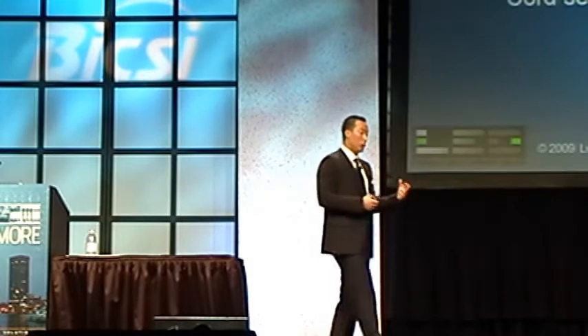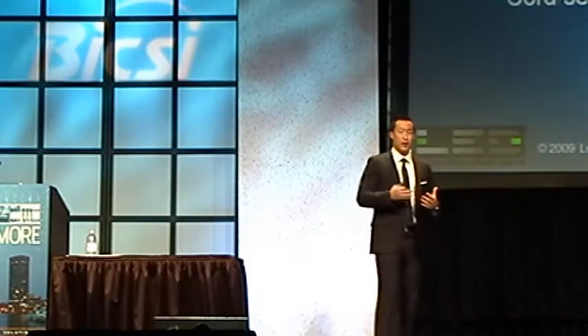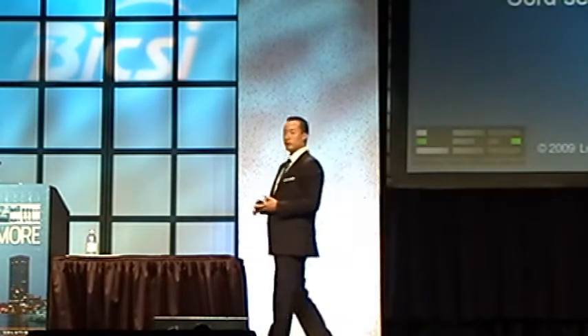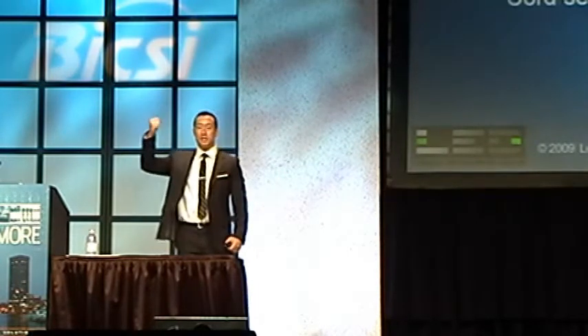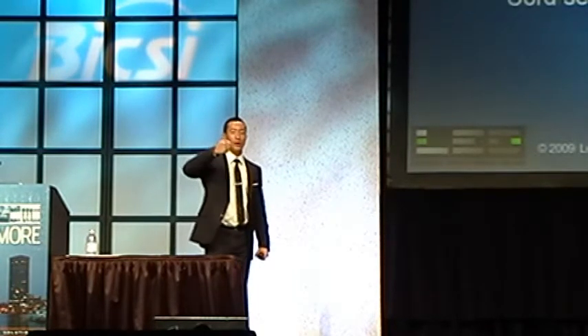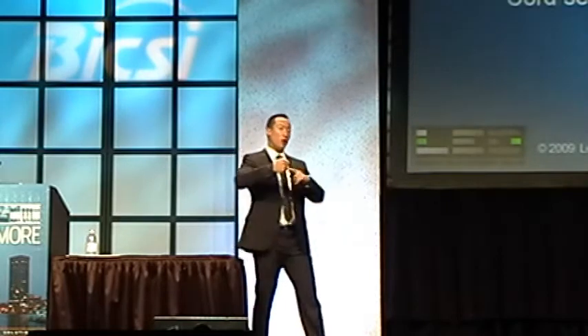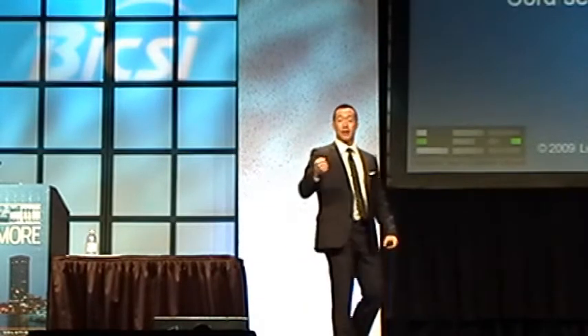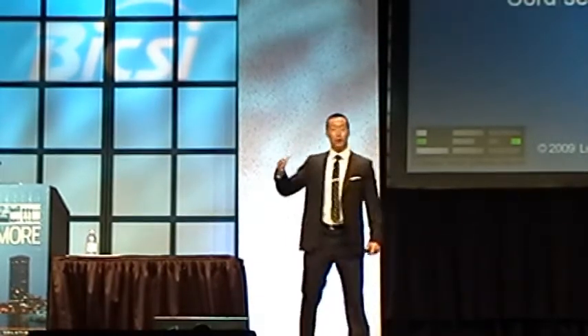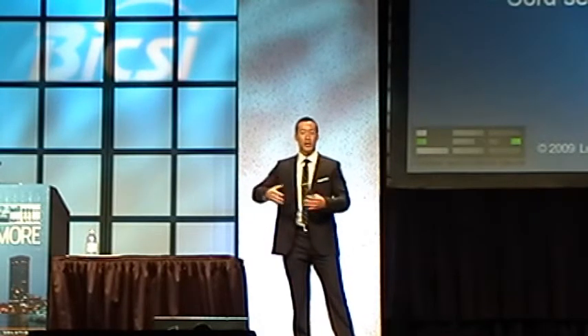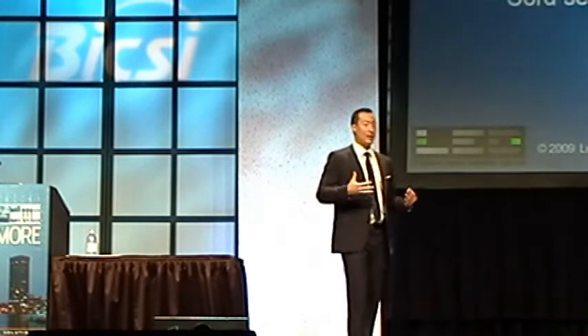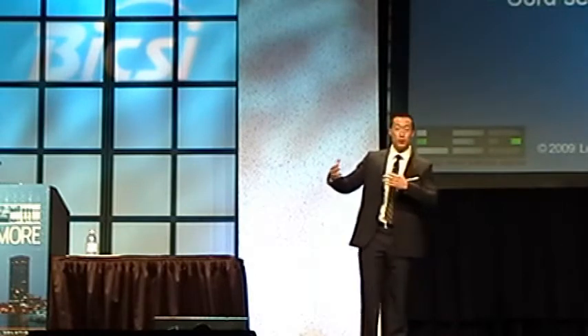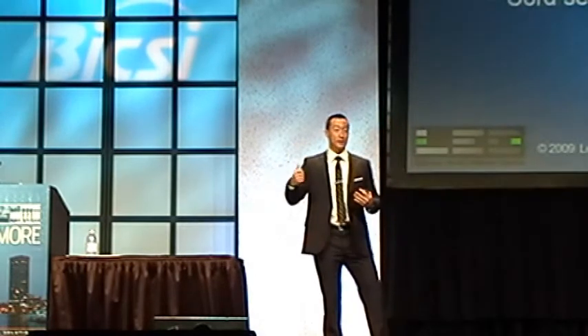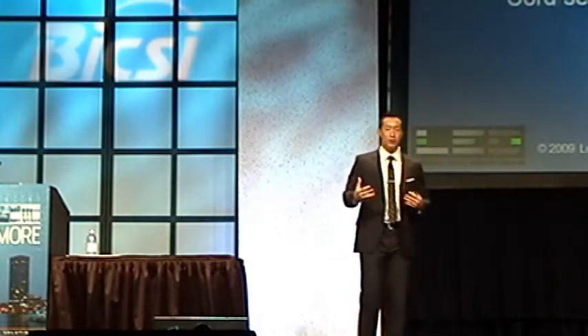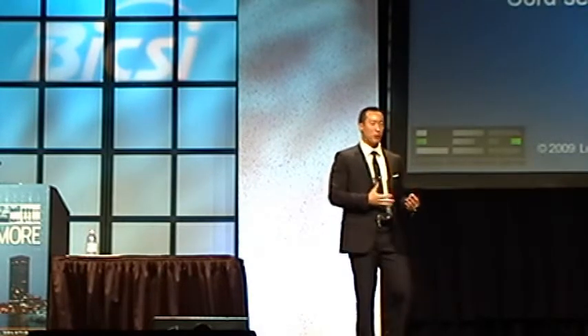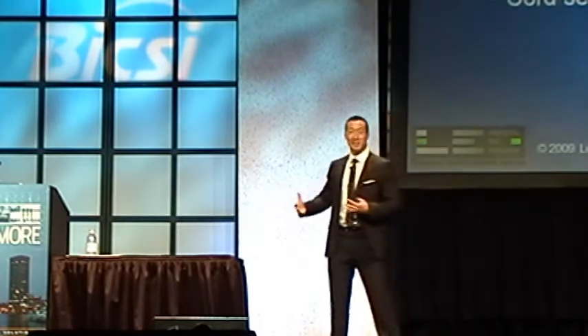In addition to that, one step further is cord set requirements, another thing that's very often overlooked. In order to power up that piece of equipment, we have to plug it in somewhere, and I'd be willing to bet that all the plugs inside the data center are not the same. What we're trying to avoid down the road is surprises. If we overlook this, and once we start populating equipment we realize we don't have the right PDUs or the right cord plug capabilities at the rack level, then we have to change it at the end of the project.